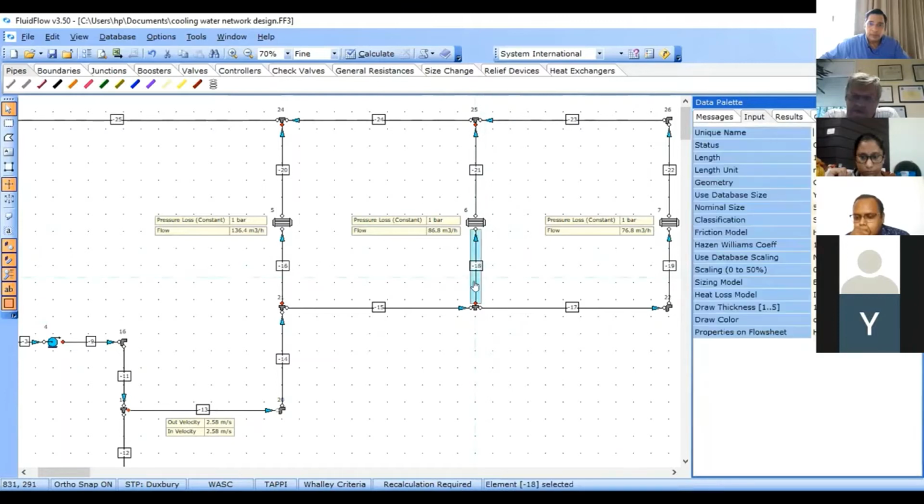Dr. Joseph was telling you can play with the pipe diameter. So here we have a 5-inch pipe. It will have some delta P. If I go for, say, an 8-inch pipe, there will be less delta P so that it will push a little more flow. But again, it will be an expensive option. So that's why we will not go ahead with that. So let us proceed with putting one restriction orifice in the outlet.